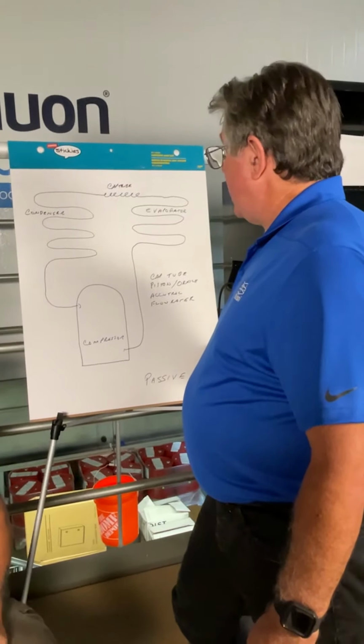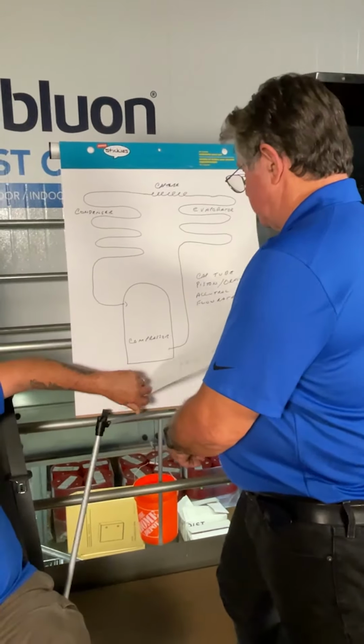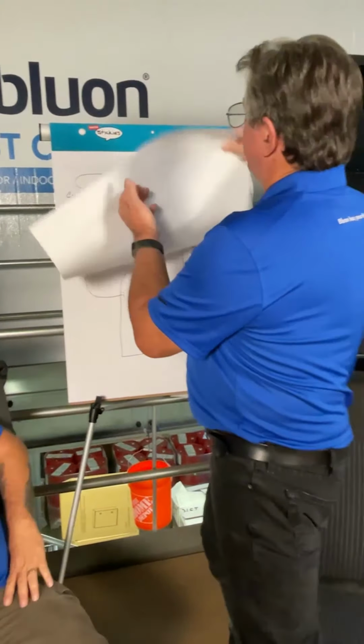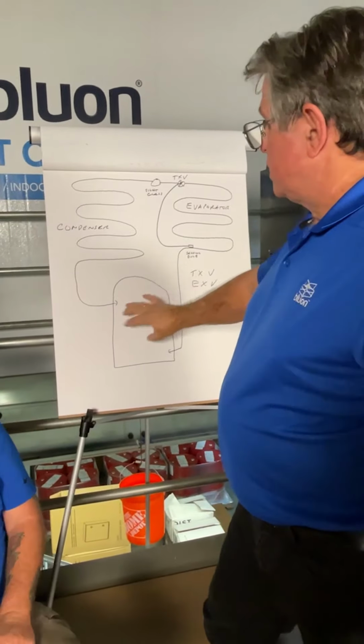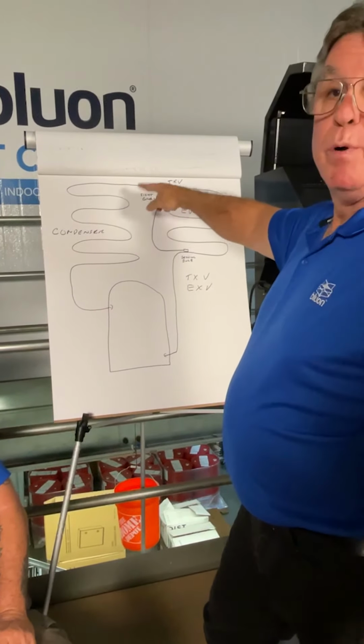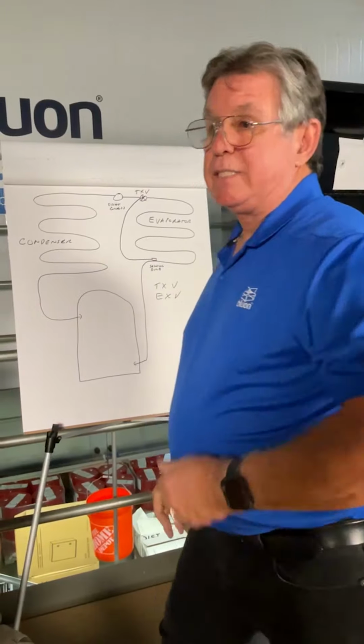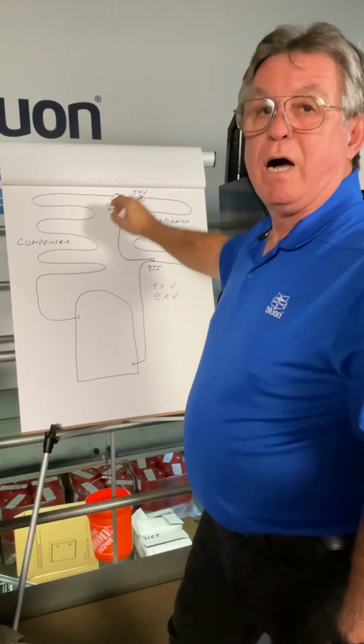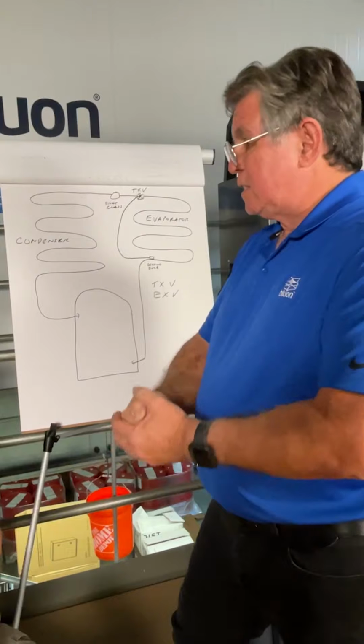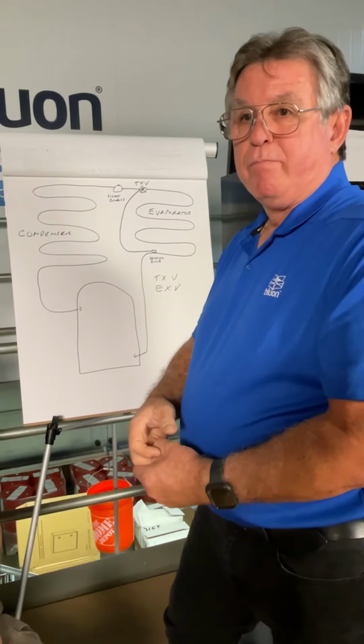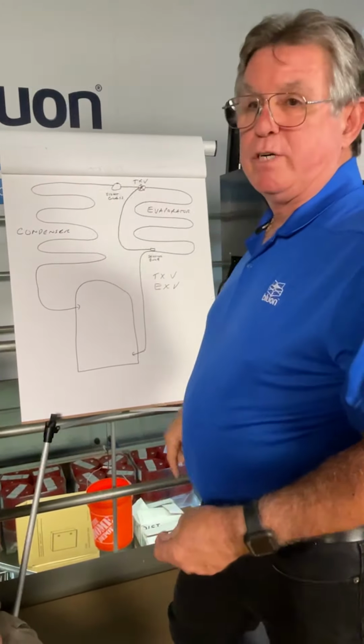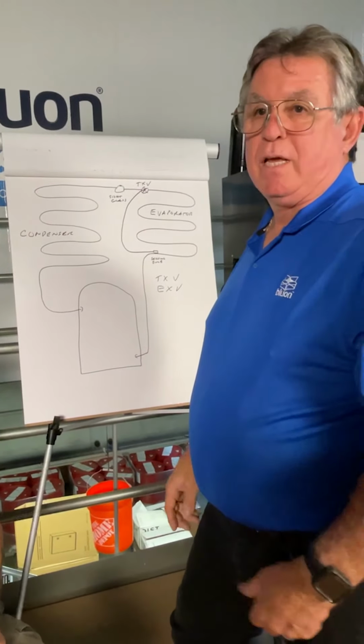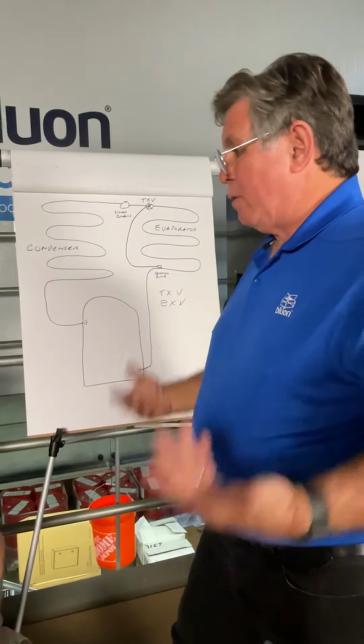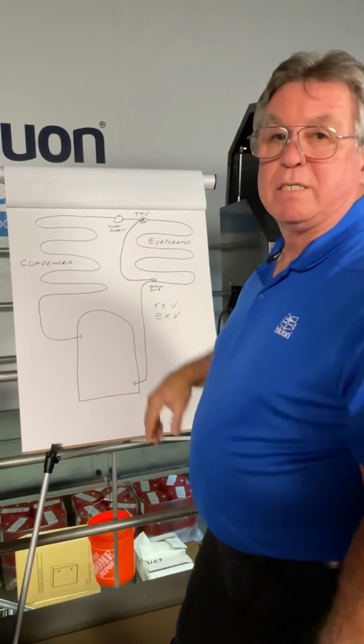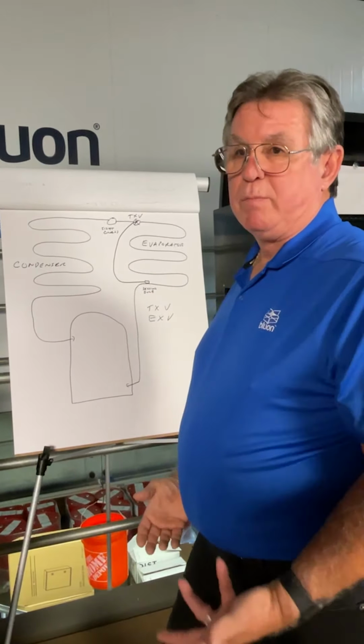So what happens, and here's the difference, is if you go to an active metering device, we still have the compressor, we still have the condenser. A lot of times I'll put a sight glass, okay? That sight glass tells us if we have a good column of liquid, a nice subcooled liquid going to that valve, because we don't want to put a saturated refrigerant through there where we're only 75% liquid and 25% vapor, because now we're not going to get the cooling. So this will tell us that we've got a full column of liquid.